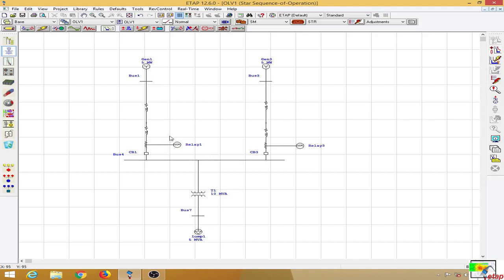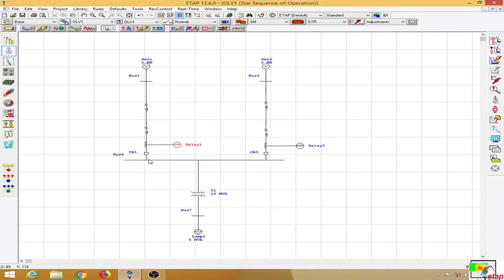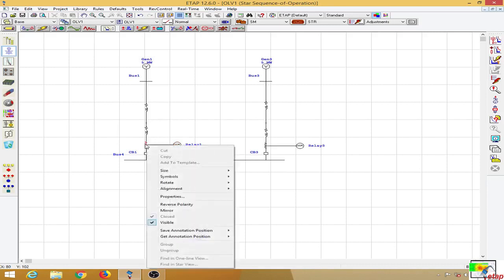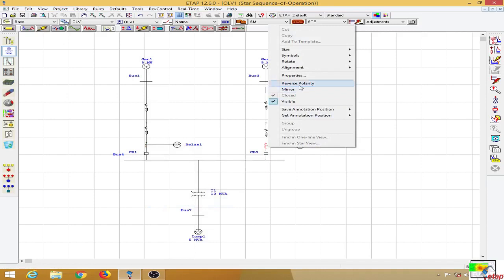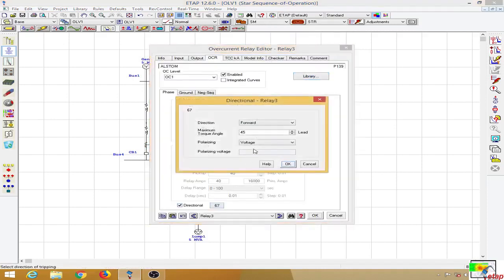This is done to avoid confusion between forward and reverse directions. I can either set the relay to the reverse direction — if the current is flowing into the non-dotted portion and we want to protect that region — or I can simply reverse the polarity of the relay. Let us stick to the conventions: I am going to reverse the polarity of these two relays and turn on the directional element for these two as well.